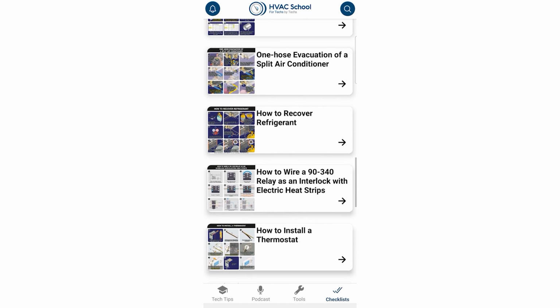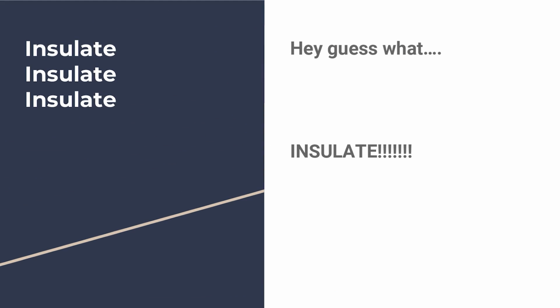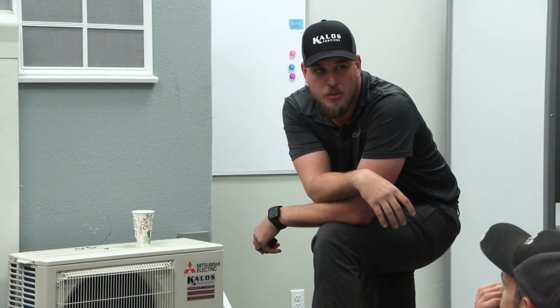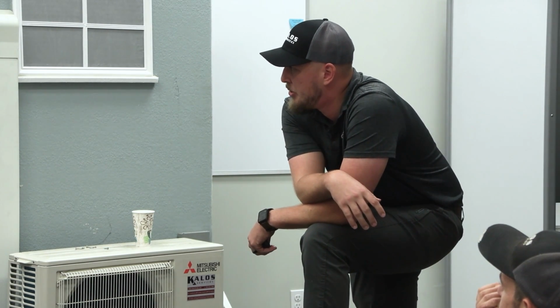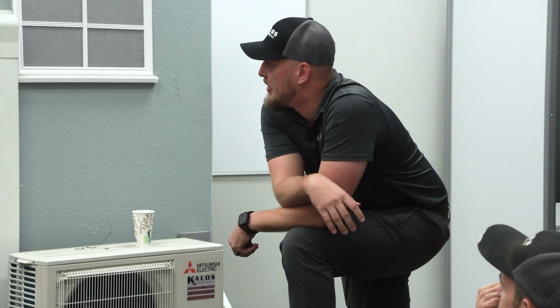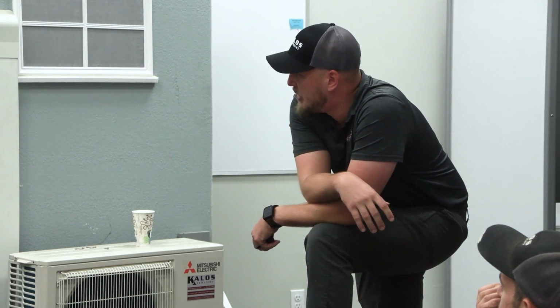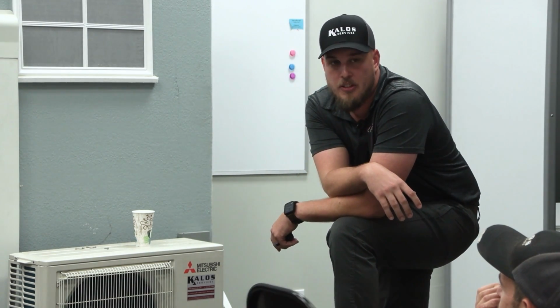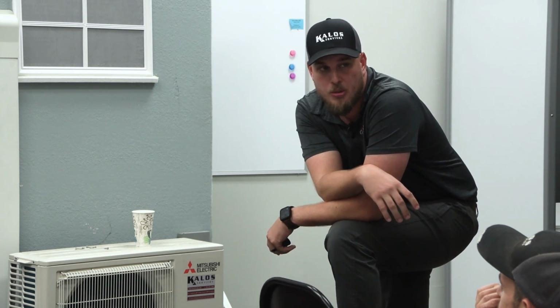All right, next, insulate, insulate, insulate. One difference between a ductless unit and a regular split: on a regular split, you have your 2 copper lines from the indoor to outdoor. One's insulated, one is not. One is cold, one is not. On a ductless unit, they're both cold. You have a suction line and you have the expansion line that run from the indoor to the outdoor, or vice versa. The EXV is located inside your condensing unit, so on the other side of that, you have that liquid vapor mix heading back to the indoor unit.